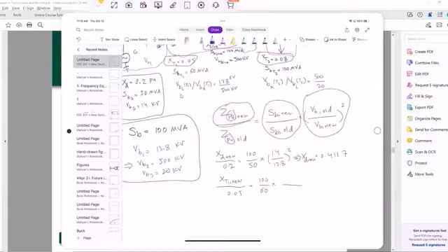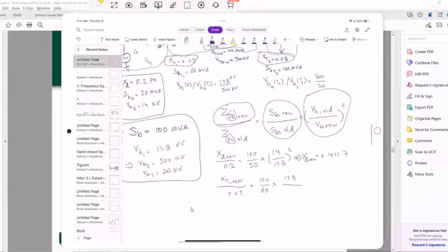we need to have the V base old. Now, if you choose the V base old on the low voltage side, you have to choose V base 1 as the new base of voltage. If you choose a V base high on transformer 1 at 500, then you have to choose V base 2. So you have to be consistent, if that makes sense. So this is equal to the old value, 13.8 over 13.8 squared. We haven't changed the base of voltage, if you noted that. Or it could be 500 over 500. So simply speaking, since we have not changed the base of voltage, XT1 new becomes 0.05 times 100 over 60, which is 0.083.